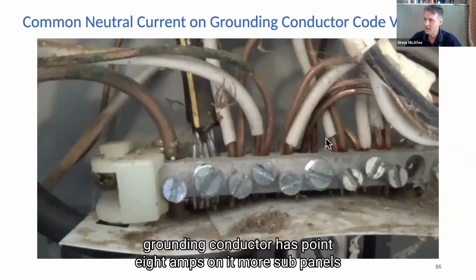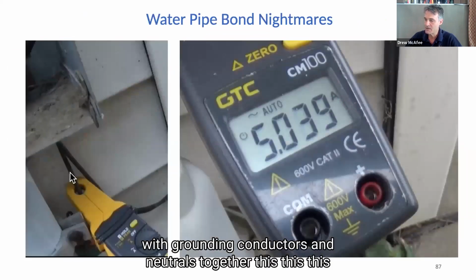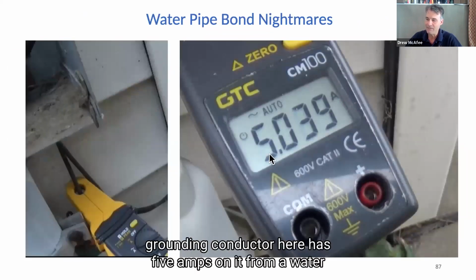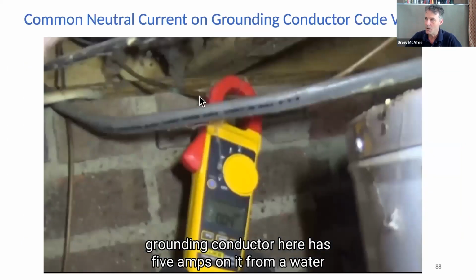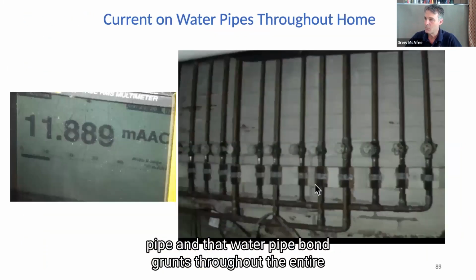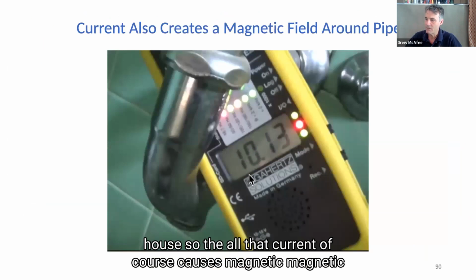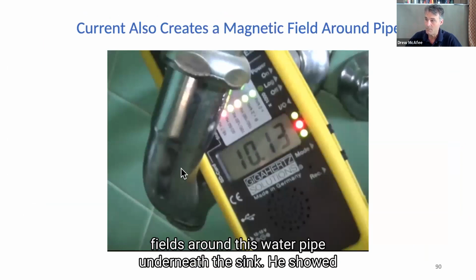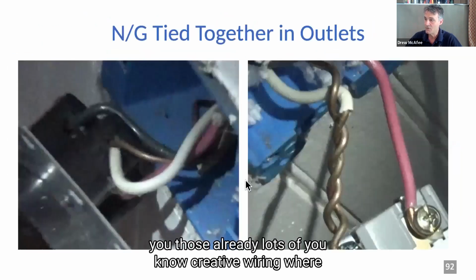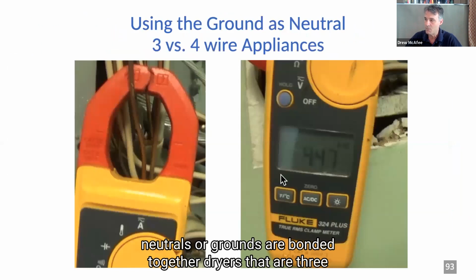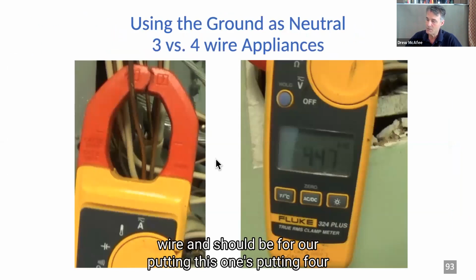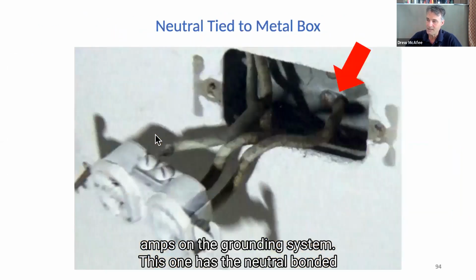More sub panels with grounding conductors and neutrals together. This grounding conductor here has 5 amps on it from a water pipe, and that water pipe bond runs throughout the entire house. So all that current, of course, causes magnetic fields around this water pipe underneath the sink. He showed you those already. Lots of creative wiring where neutrals and grounds are bonded together. Dryers that are 3-wire and should be 4-wire; this one's putting 4 amps on the grounding system.